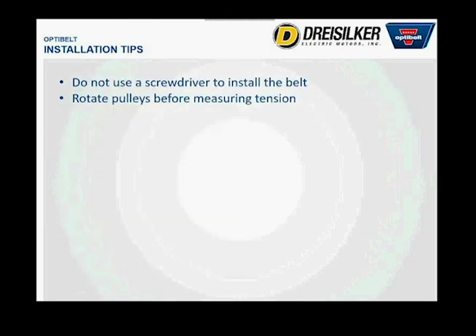So just a couple installation tips. These are issues we see all the time and generally don't recommend: do not use a screwdriver to install the belt. A lot of the times, a lot of these machines, especially on rooftops, are very difficult to fit the belt over the pulley. There's not a lot of room for adjustment, and you usually have to remove some pieces just to do it.